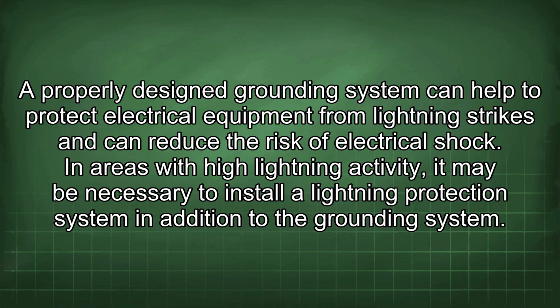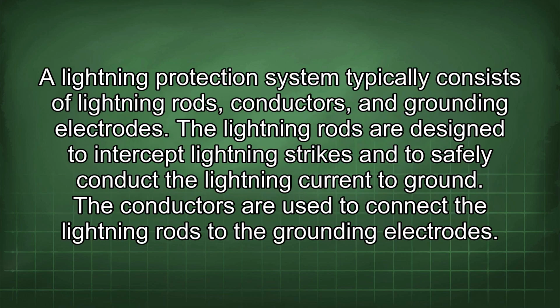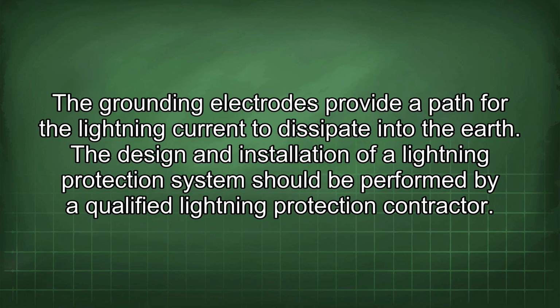to the grounding system. A lightning protection system typically consists of lightning rods, conductors, and grounding electrodes. The lightning rods are designed to intercept lightning strikes and to safely conduct the lightning current to ground. The conductors are used to connect the lightning rods to the grounding electrodes. The grounding electrodes provide a path for the lightning current to dissipate into the earth. The design and installation of a lightning protection system should be performed by a qualified lightning protection contractor.